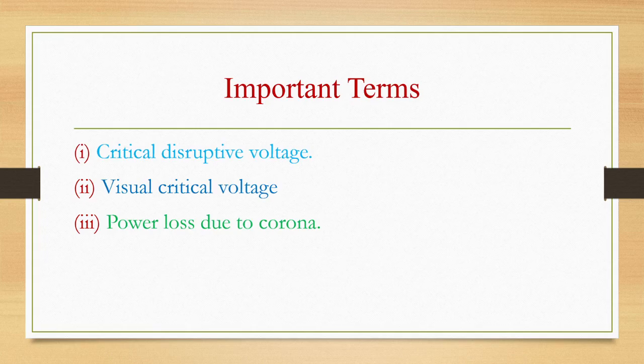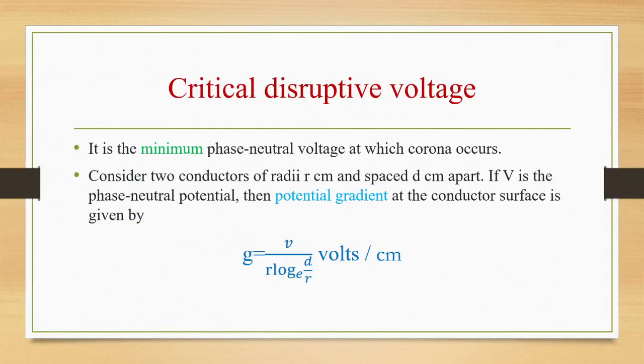Okay students, let us start with the first one, that is critical disruptive voltage. It is the minimum phase neutral voltage at which corona will occur. Consider two conductors of radii r centimeter and they are spaced d centimeter apart. If V is the phase neutral potential, then the potential gradient at the conductor surface is given as g equal to V by r log d by r base e. Units are volts per centimeter.